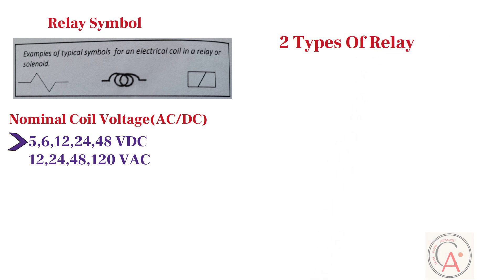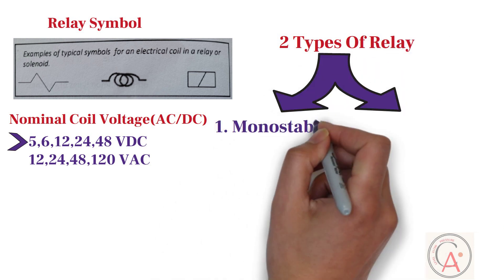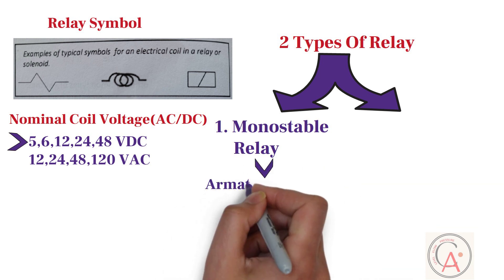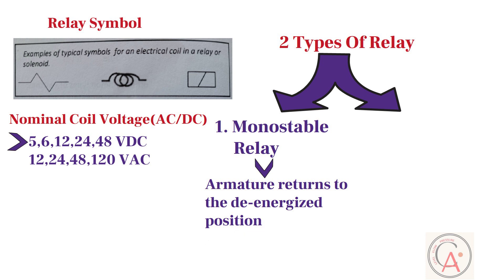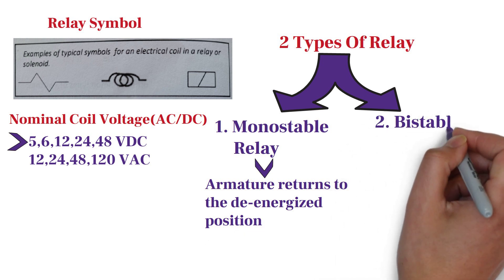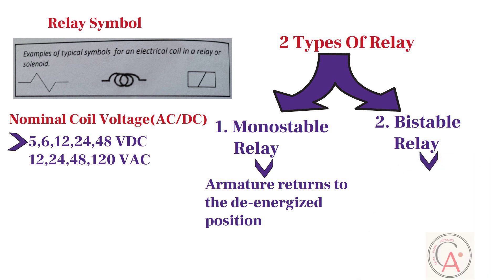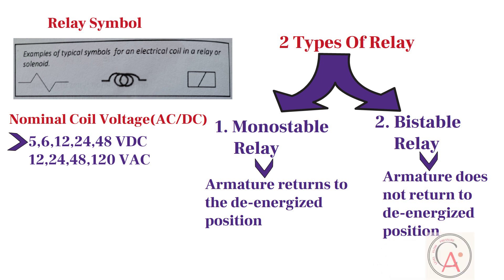There are mainly two types of relay. The first type is the monostable relay. In a monostable relay, the armature returns to the de-energized position when the coil voltage is removed. The second type is the bistable relay. In a bistable relay, the armature does not return to the de-energized position when the coil voltage is removed — in other words, the relay is latched on and needs another signal to reset the relay.